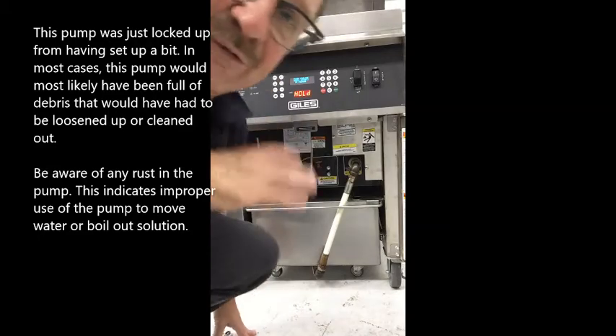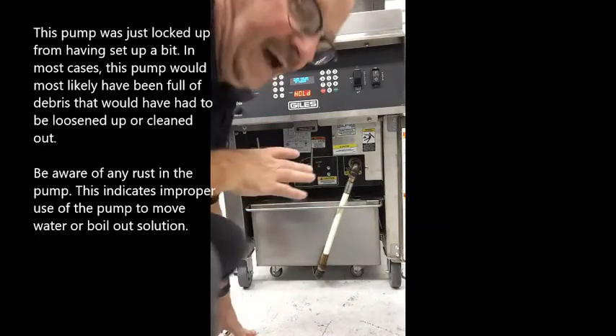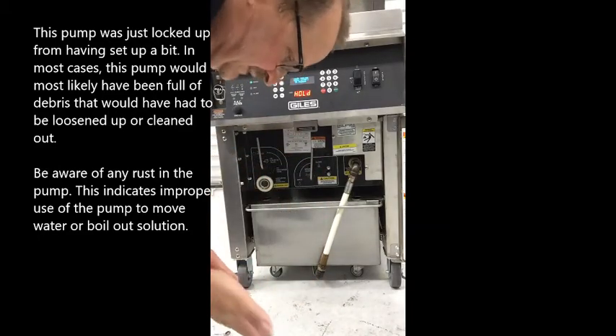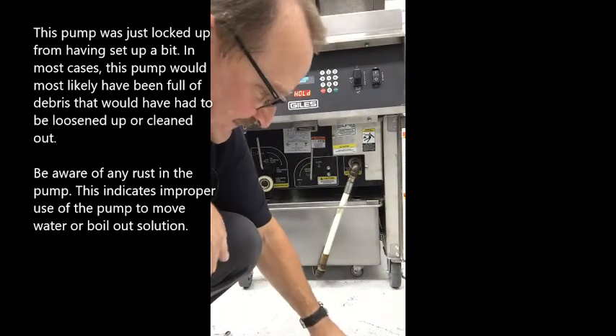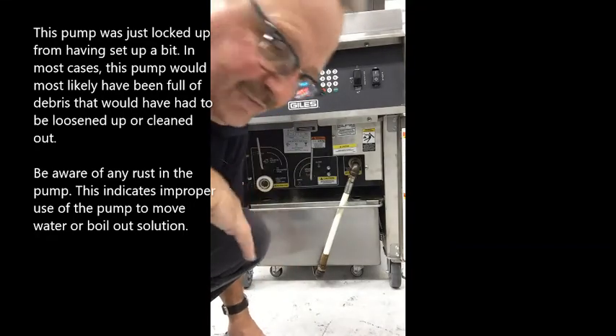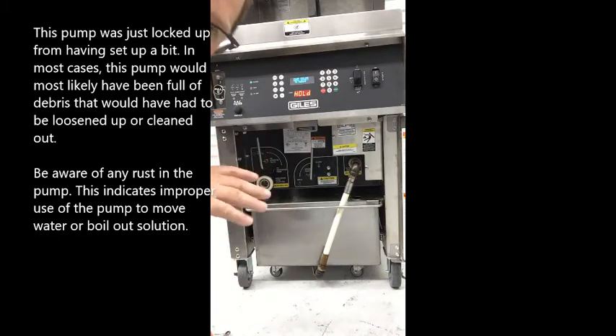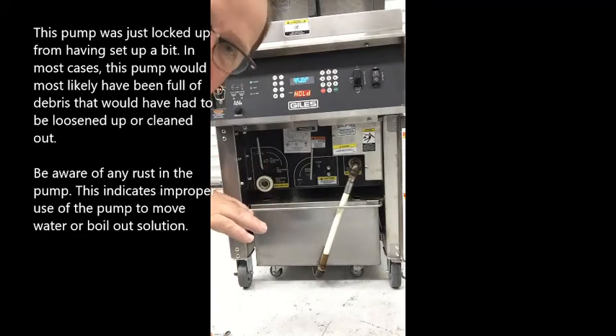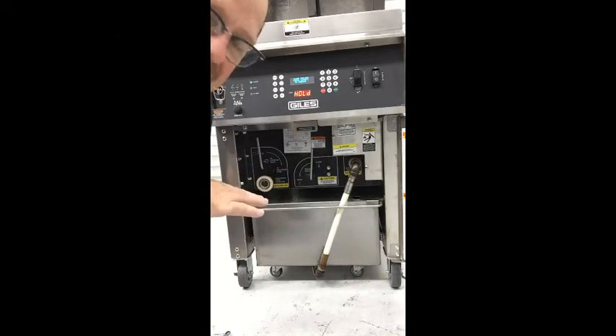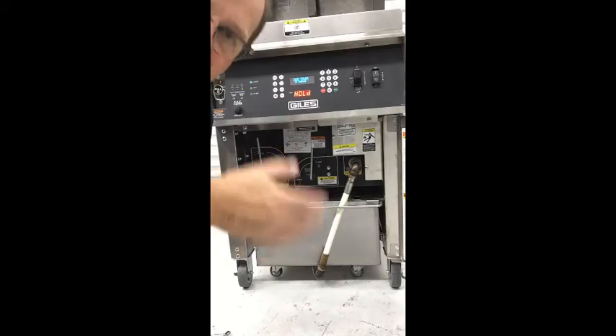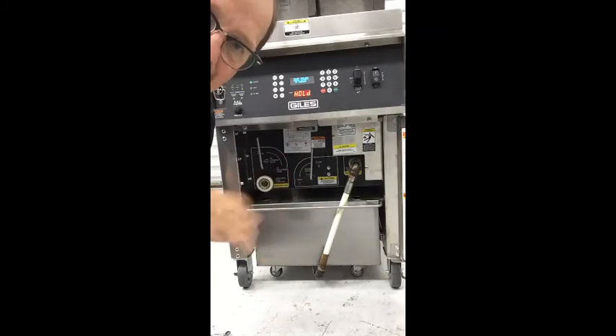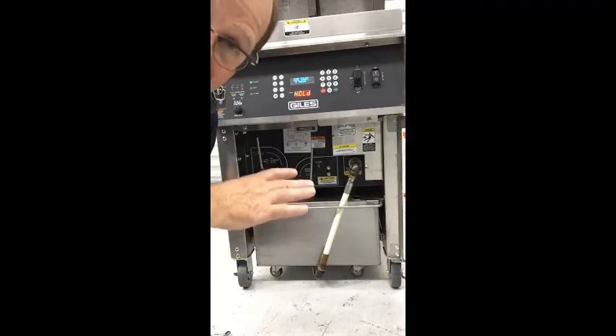So that's how you get your pump to go. It's not always that easy, but in most cases, that's all it takes. Now these pumps have a thermal overload in the motor. So sometimes what will happen is the motor will actually kick off. It has to cool down, it'll come back on. It'll kick off, cool down, come back on. And you'll hear that from the customer.